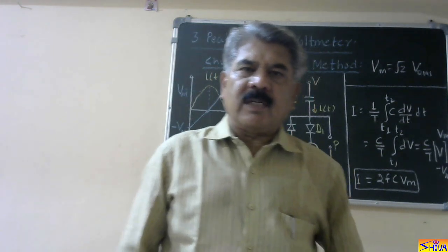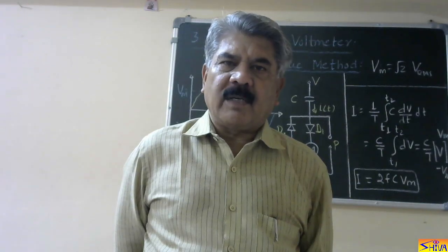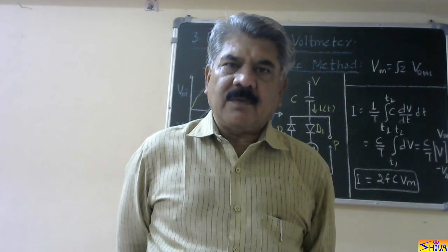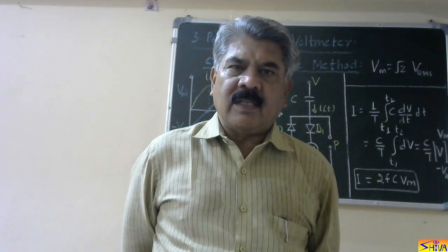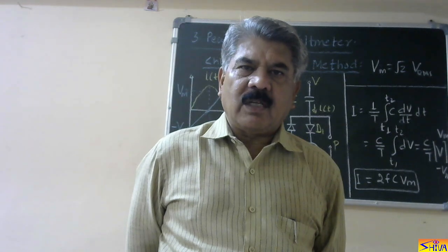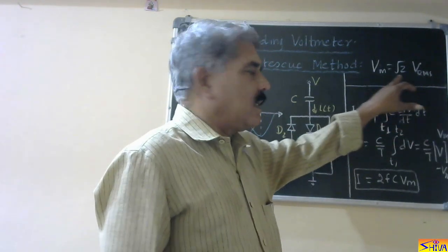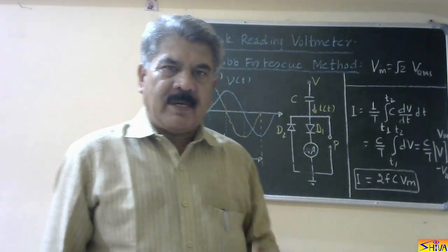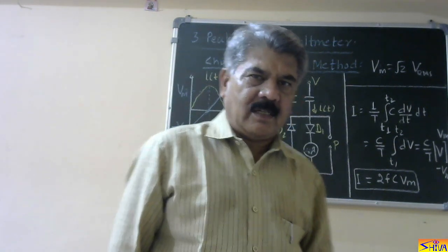In case of high voltage testing, whenever breakdown, flashover or spark over of the test object takes place, it is always at the peak value. Therefore, during high voltage testing, it is necessary to know the peak value. And if the voltage waveform is not sinusoidal or it contains harmonics, then this relation is not valid. Therefore, we need a separate peak reading voltmeter in high voltage testing.